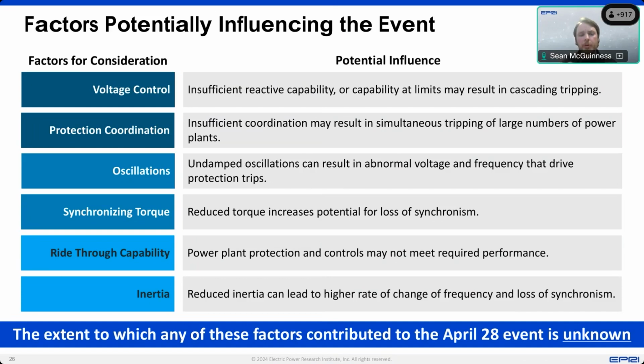We put in here synchronizing torque, which personally I feel kind of gets in the shadow of inertia. Everyone talks about inertia being the problem, but when you are operating a grid with a lot of grid-following resources from inverters and you're reducing the number of synchronous generators, it's important that those synchronous generators are tied together, and synchronizing torque is what keeps them in synchronism. If there are two generators very remote from each other and one trips, the other may not respond quickly and you can have a loss of synchronism.